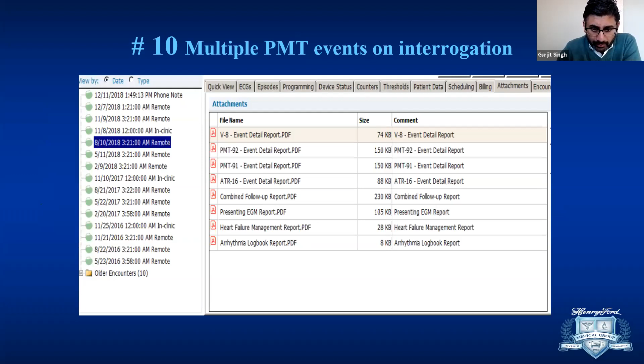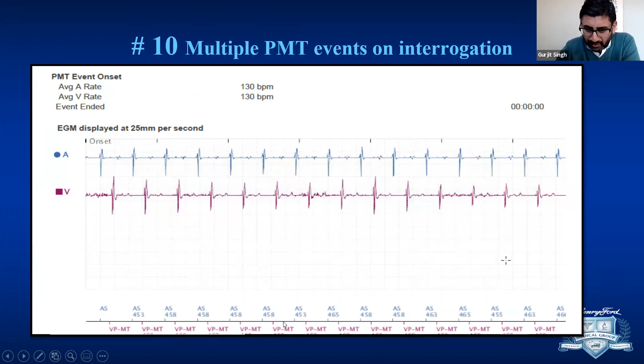Multiple PMT episodes were recorded on this patient. And here is the electrogram of one of those episodes, and shown here is the atrial channel and the ventricle, and you can see it's A-sensed and V-paced at max track, okay? Usually PMT will start at the max track rate, and that's how the pacemakers know that a PMT might be happening, okay? So let's see how the pacemaker intervenes.